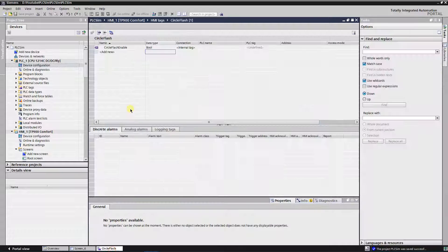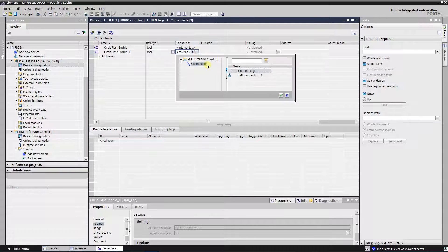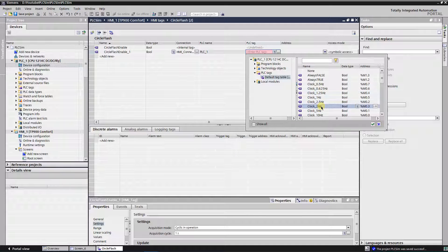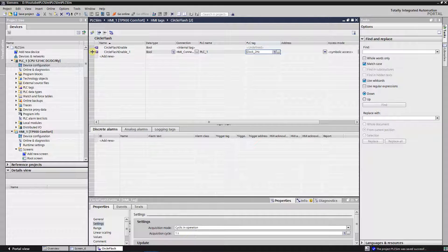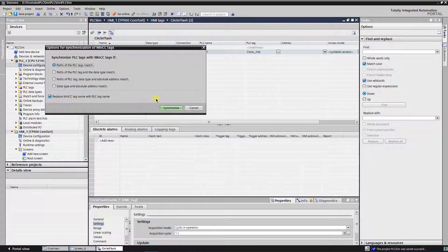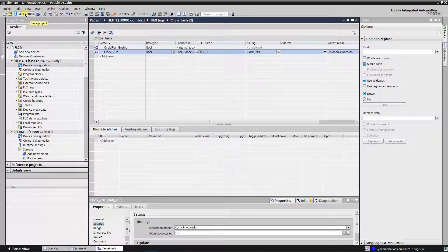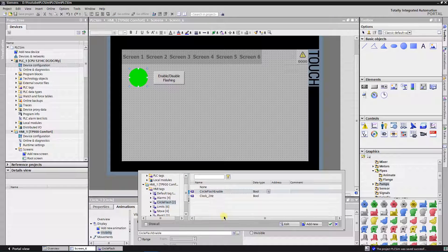Let's add one bit out of the clock memory byte — its state will toggle on a regular interval. Open the HMI tags table and click on add new. Do not worry about the name of the tag for now. Select the configured PLC HMI connection instead of internal. Expand PLC tags and find one from the clock memory area — let it be of the frequency of 2 Hz. Click on synchronize with a PLC tag and the name of the tag will be changed according to the PLC tag name. Switch back to the screen with the object. Select the circle, switch to the animation tab and select animation visibility. Replace the process tag with the newly created PLC tag.